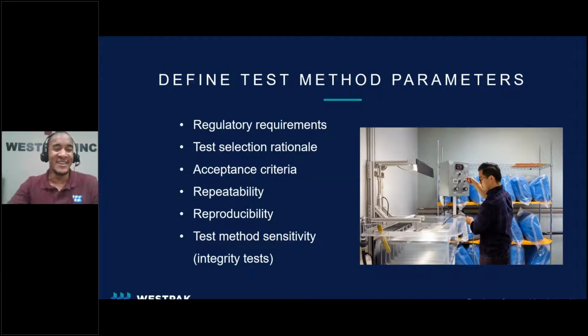For qualitative tests, like gross leak testing, the data that is generated is an observation based on defined characteristics, like a breach in the sterile barrier. The acceptance criteria for quantitative tests, on the other hand, like seal strength testing, will depend on a data set that is produced after completing the test and must fall within a defined range. If the operator is able to identify the known defects for qualitative tests and produce a data set that falls within the acceptance range for quantitative tests, this will then provide evidence that the test method is repeatable and reproducible.